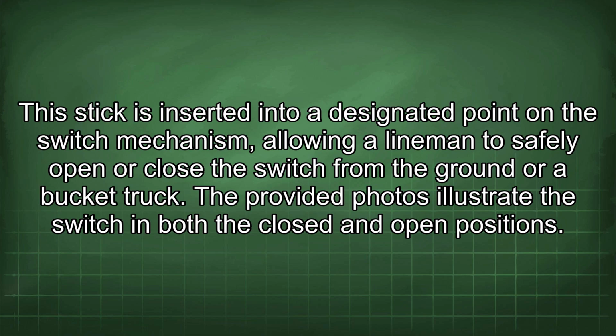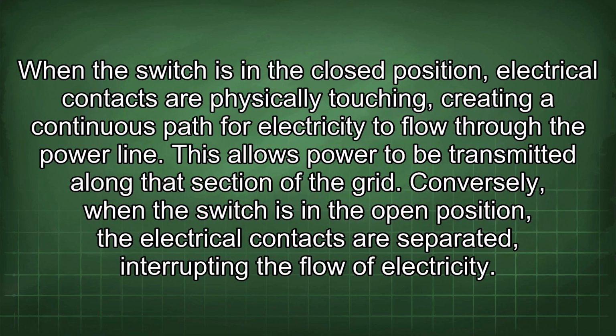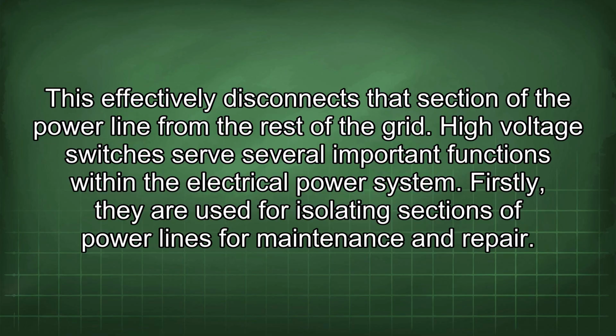The provided photos illustrate the switch in both the closed and open positions. When the switch is in the closed position, electrical contacts are physically touching, creating a continuous path for electricity to flow through the power line. This allows power to be transmitted along the section of the grid. Conversely, when the switch is in the open position, the electrical contacts are separated, interrupting the flow of electricity. This effectively disconnects that section of the power line from the rest of the grid.